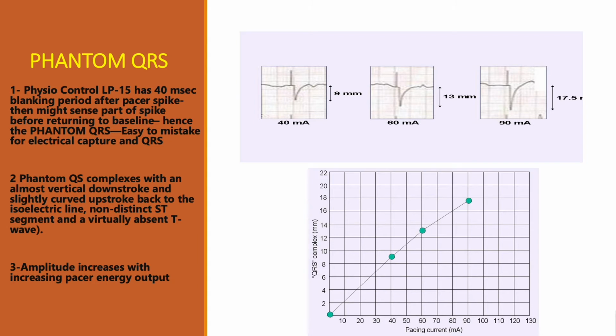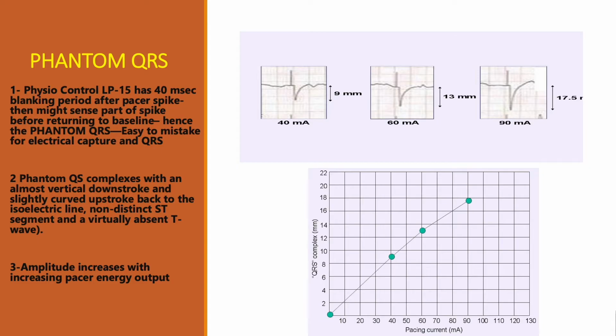The other clue is the voltage of these phantom QRSs, so how high or low, what the distance is here and here and here. As you increase your output, the milliamps on the Physio Control, they get bigger, where that's not going to happen if it's just a true myocardial response to it. So see how this happens at 40 milliamps, its response is here, at 60 milliamps, it's bigger, at 90 milliamps, it's actually bigger than that too.